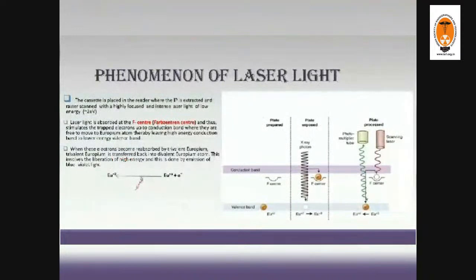Now let's go to the processing of latent image in computed radiography. The CR cassette with the latent image is placed in the reader and the PSP is extracted and raster scanned with intense red laser beam. The laser beam stimulates the electrons trapped in the F center, and these electrons leave the high energy conduction band to lower energy valence band, and these electrons are reabsorbed by the europium atoms. This involves the liberation of high energy, and this is done by the emission of blue-violet light.